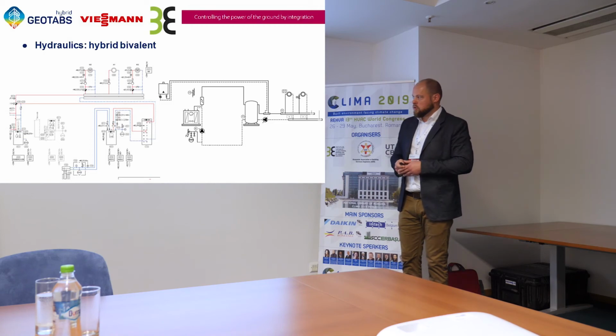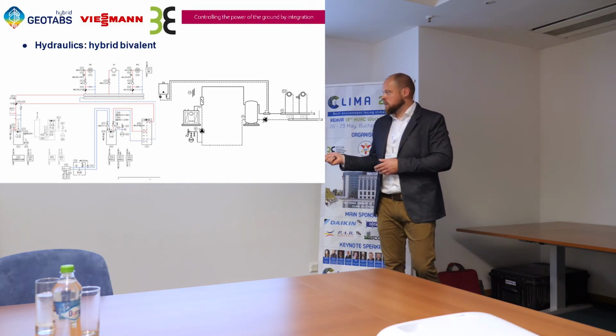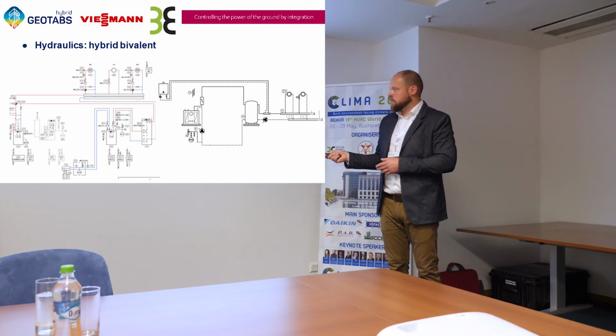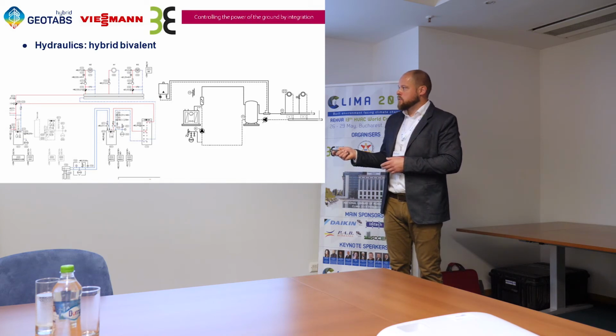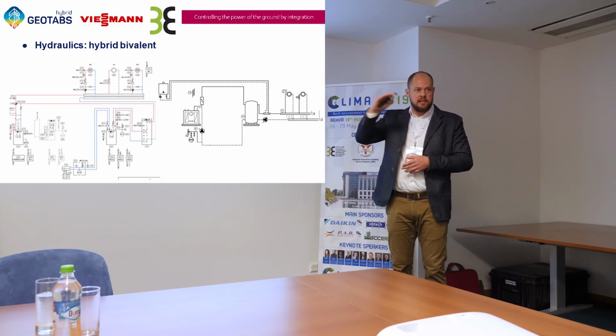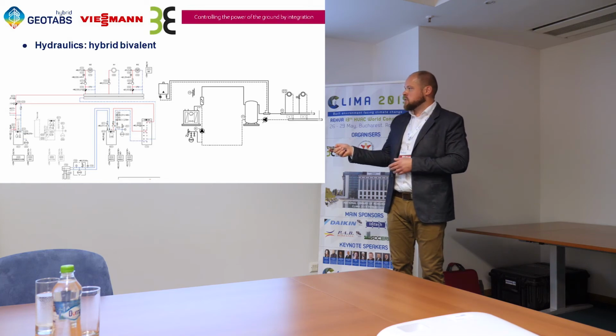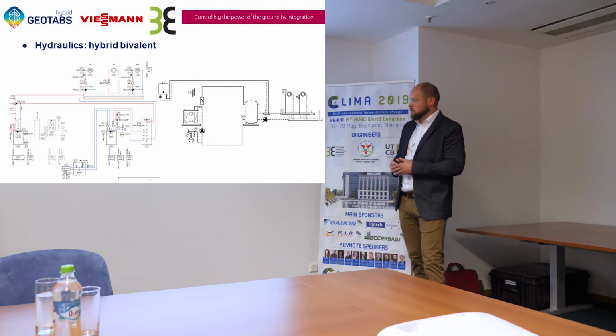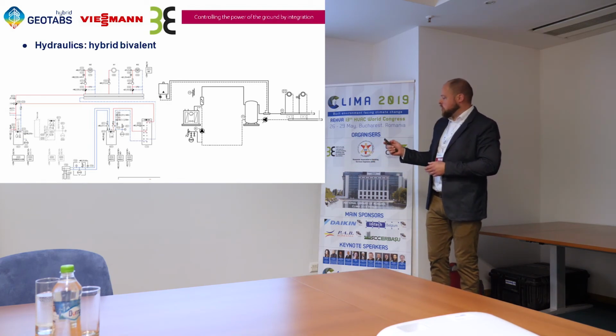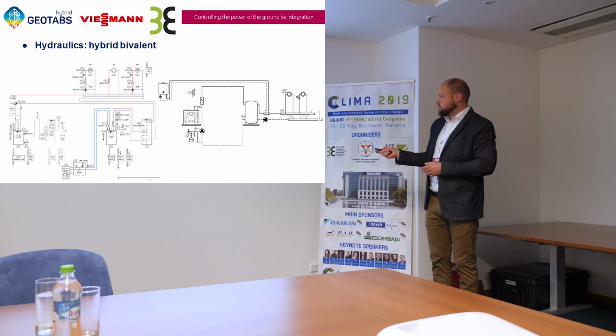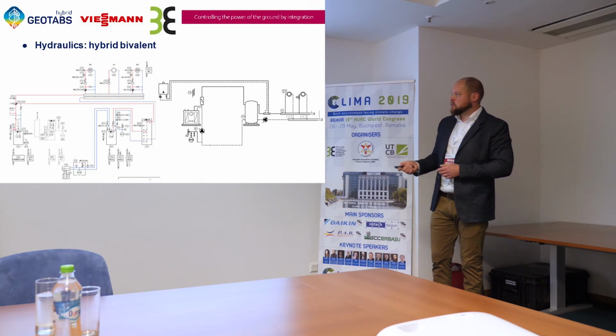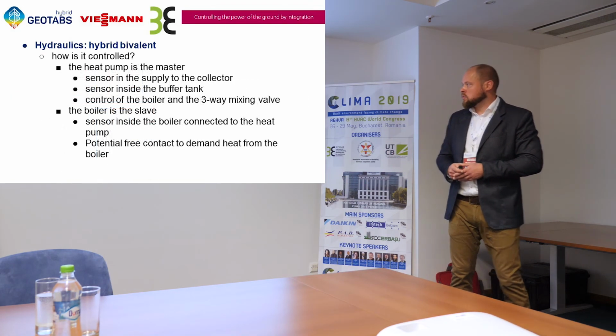And the control of that mixing valve is done by the regulation inside the heat pump. So the heat pump will measure the temperature here. It will see if the temperature is as demanded, and if the temperature is too low, it will activate the gas boiler and then control this valve to mix extra heat into the departing line through the installation. You can also work with this type of system. That's another option. It's not used by us.